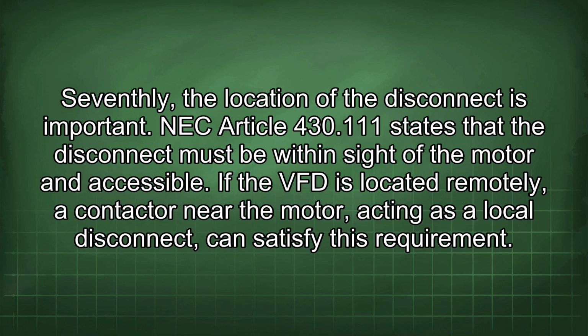Seventhly, the location of the disconnect is important. NEC Article 430.111 states that the disconnect must be within sight of the motor and accessible. If the VFD is located remotely, a contactor near the motor acting as a local disconnect can satisfy this requirement.